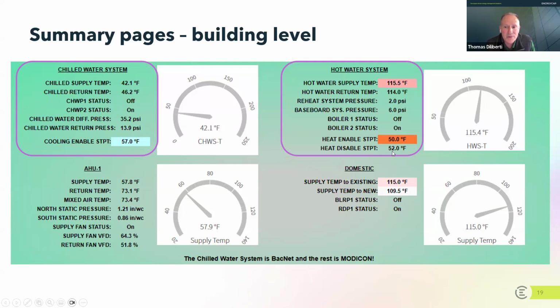So we've created a temperature band between 52 and 57. It's this idea of a dead band again, where the system is not going to actively heat or cool. It's simply going to coast along. And this is a great strategy for energy conservation, is to create this band of temperatures where your building can't heat and it can't cool because it's so mild outside. And this is going to be unique by building and by system, but this is something that you should definitely be aware of and understand in your buildings, is when they enable and when they disable.